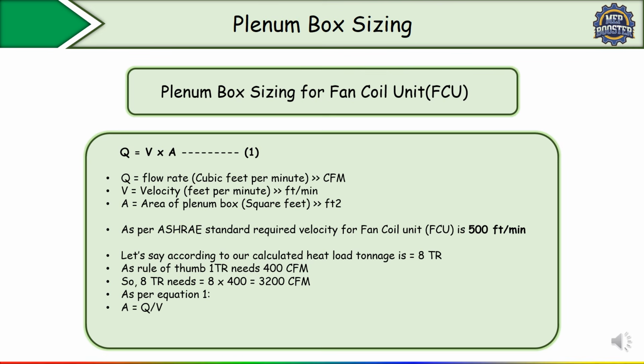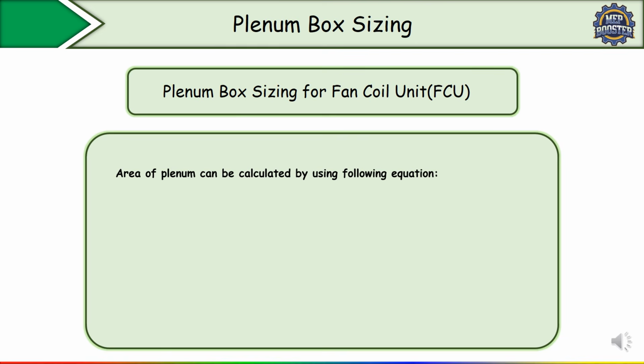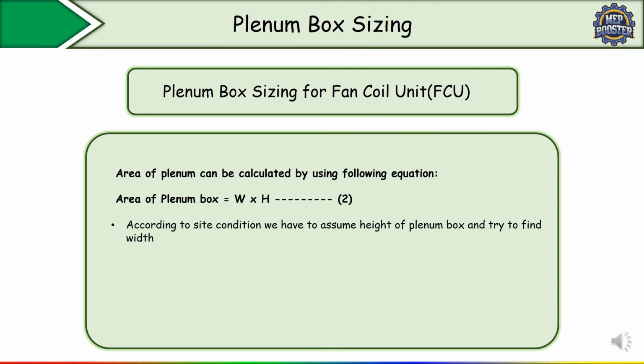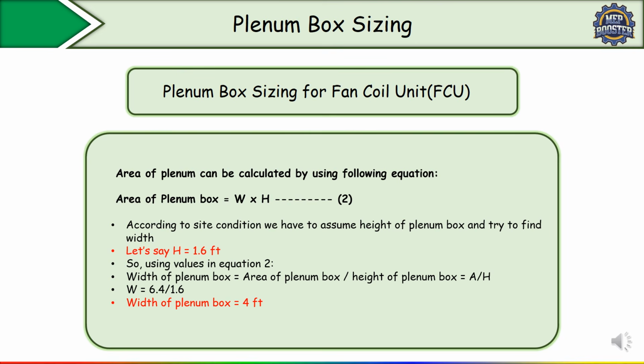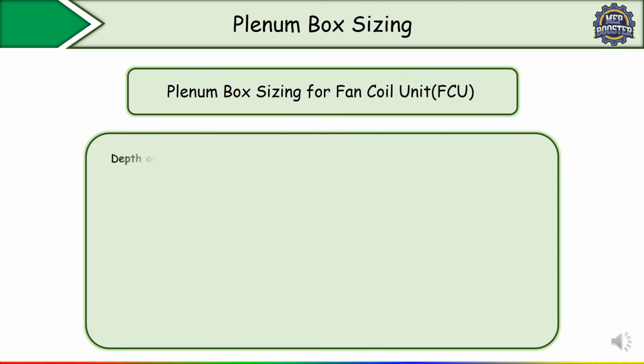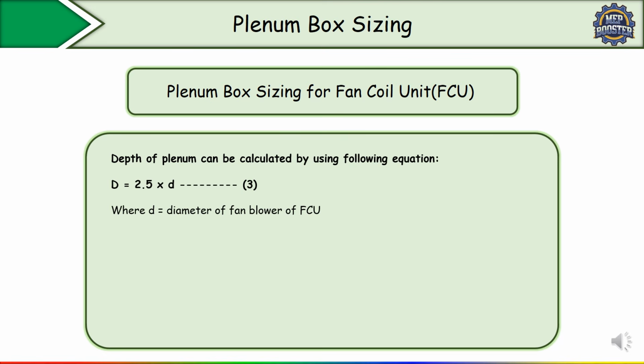Now to calculate the area, the simple formula is A equals Q upon V. When you substitute the values, we get an area of 6.4 square feet. As I already discussed, the area of the plenum can be calculated using the equation given, which is our equation number 2. Now finally, according to site conditions, we have to assume the height. Here I have taken 1.6, the same height. When you substitute, you get the width of 4 feet. In the same way, to calculate the depth of the plenum box, it is 2.5 times the blower diameter of the FCU, correct? Here I am assuming the same, the diameter of the fan blower of the FCU is 12 inch. When you substitute, you get the depth of the plenum box as 2.5 feet. In this way we need to calculate the plenum box sizing for a fan coil unit.